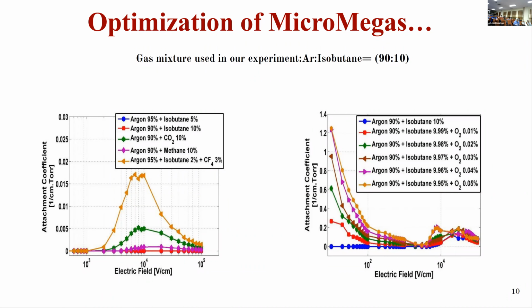And that is the reason we work with argon and isobutane in this proportion, at least in the institute. Now, other things to look for: here you could see that if we have even a little amount of O2, the attachment coefficient is quite high, it increases. So ideally, we would want our detector to be leak proof so that there is no oxygen going inside it.